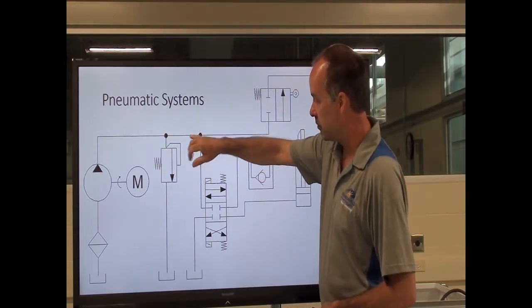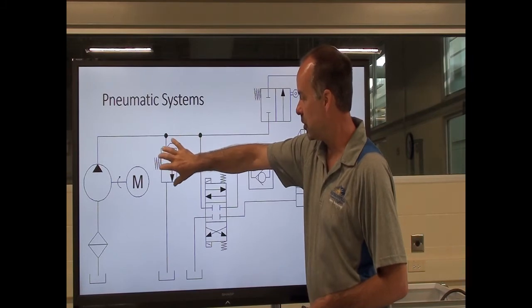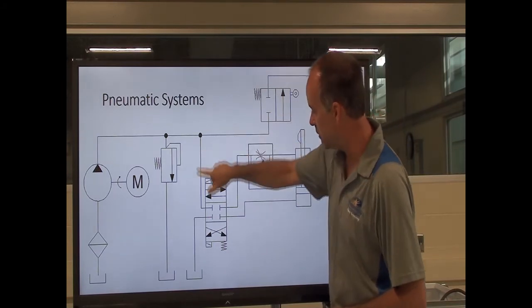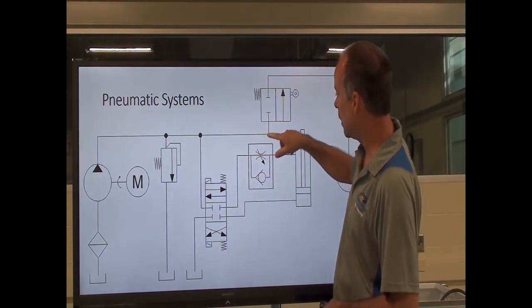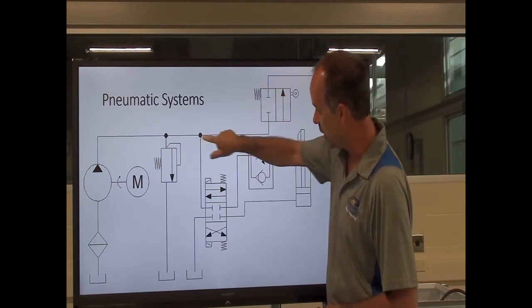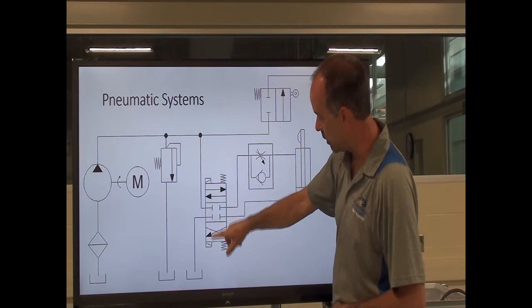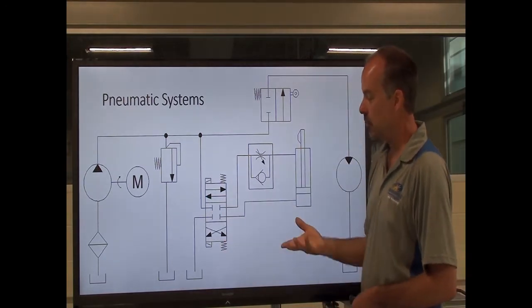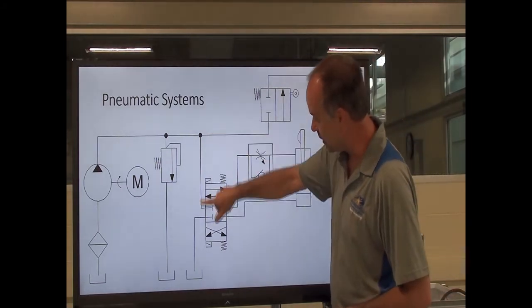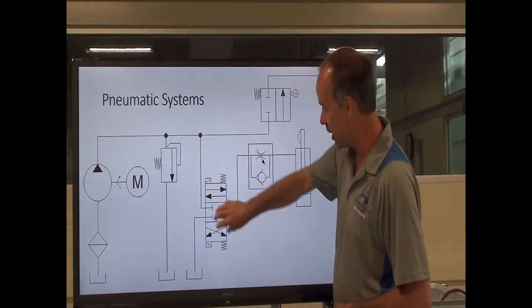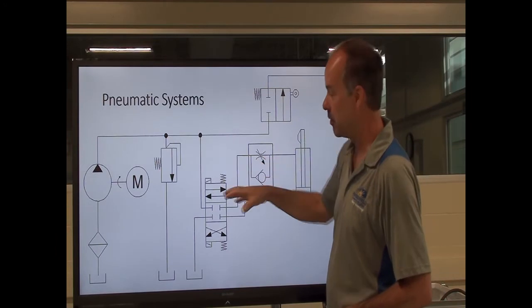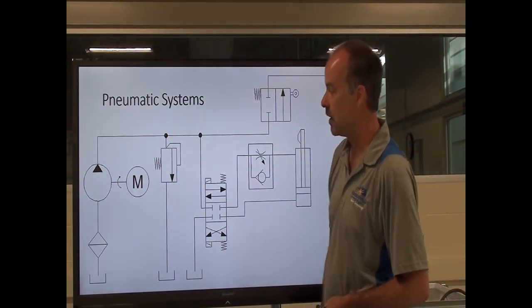Going beyond this, now that we've set the system pressure using our relief valve, we have fluid going to a couple DCVs. Up here we're going to a blocked port, so there's no fluid flowing in this current state. Then we follow down to this port on our three-way, or four-way, three-position DCV. This port is blocked because we have a closed center on this DCV. In this normal state, there's no fluid flowing.